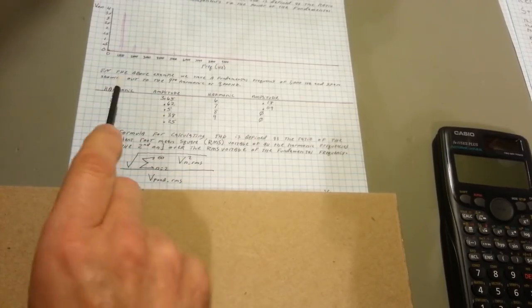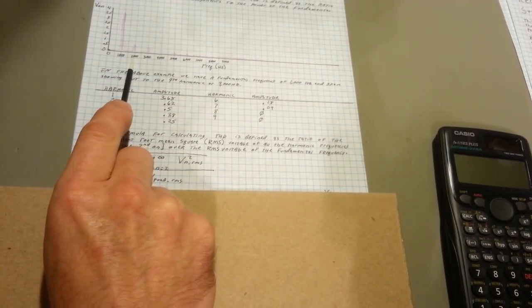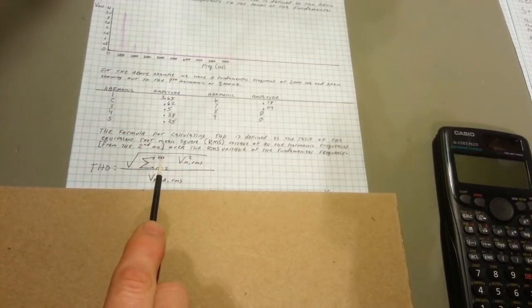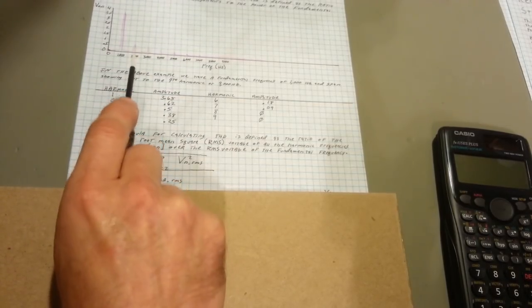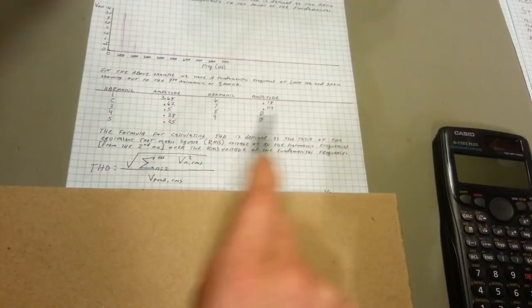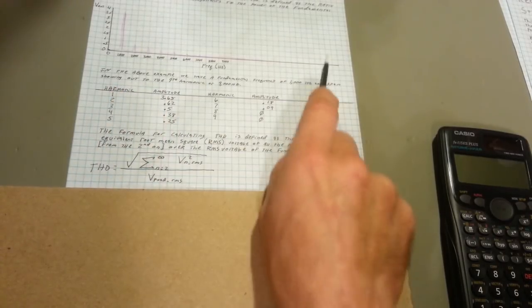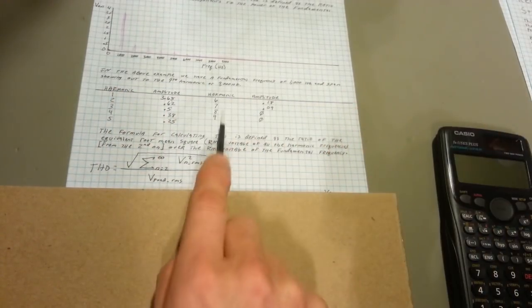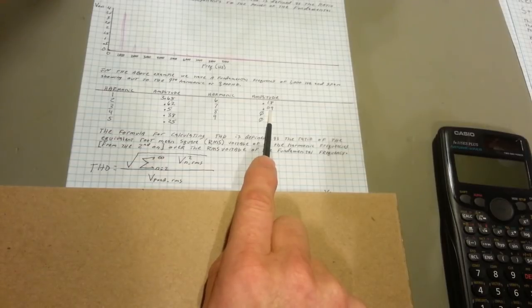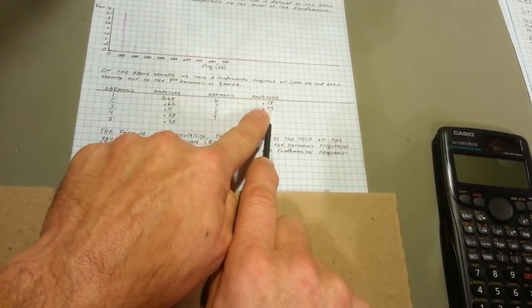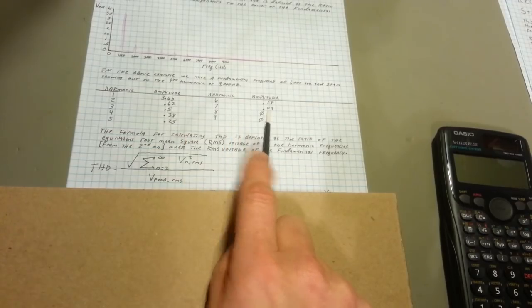So that's the first thing we're going to be measuring, from the second harmonic, and that is the infinity symbol, because actually you'd be measuring out to infinity. But like I say, in reality, we don't have anything measurable out any farther than the seventh harmonic. So that's all the farther we need to go. We don't need to go to infinity. There's nothing measurable past the 7th harmonic.